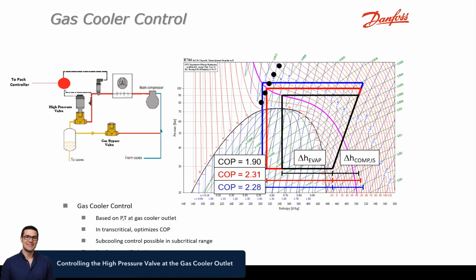We take these values, and based on what that temperature is, we define in the controller what the optimal pressure is, right here also at the outlet of the gas cooler, for the transducer that we would have. Figuring out that optimal point is what drives the opening degree of the high pressure valve. And so you get 3 refrigeration cycles that you can see in the slides here, where we've defined a specific temperature out of the gas cooler, which would be this pinkish line highlighted in the middle of the 3 refrigeration cycles. We've picked 3 different points on our pressure, which would be the pressure at the outlet of the gas cooler, and that's the top part of each refrigeration cycle.